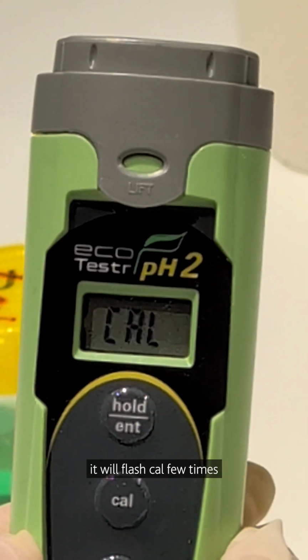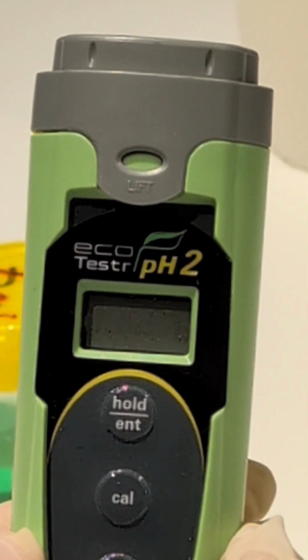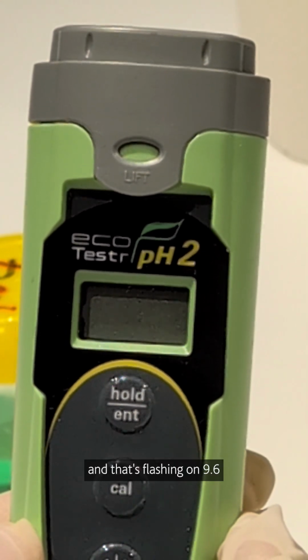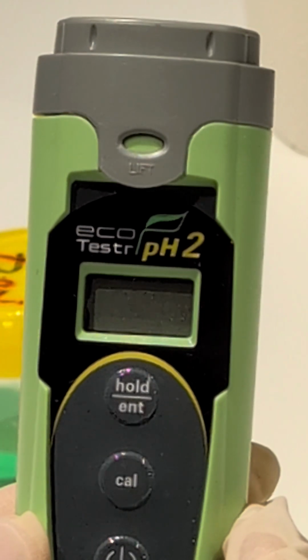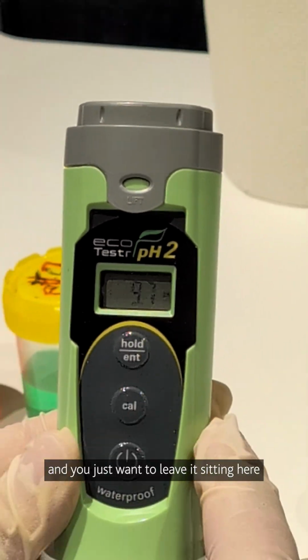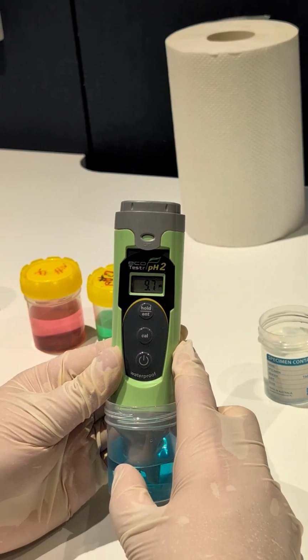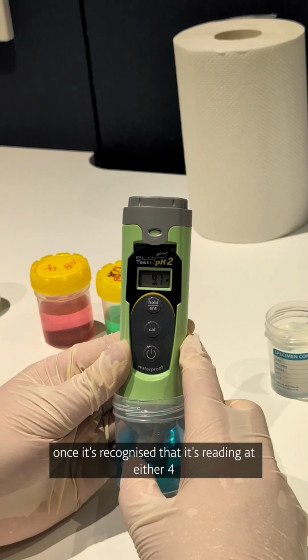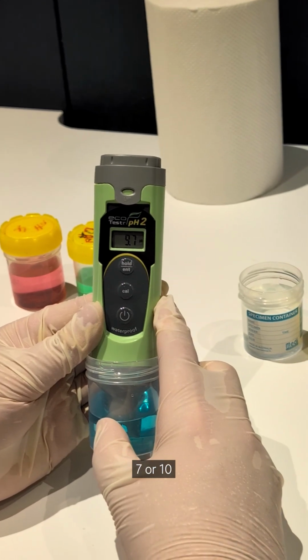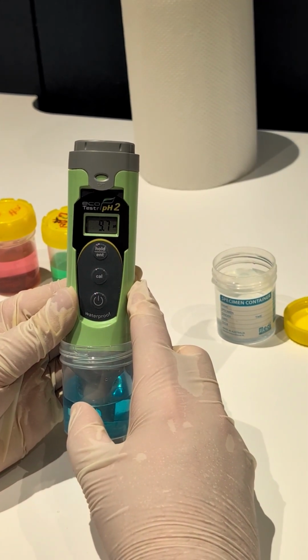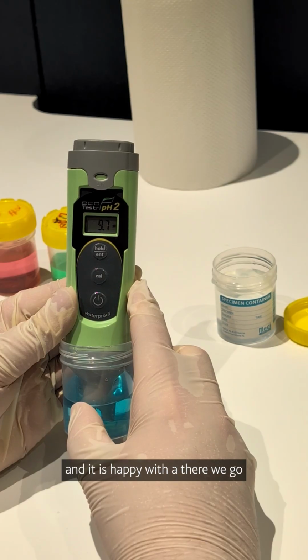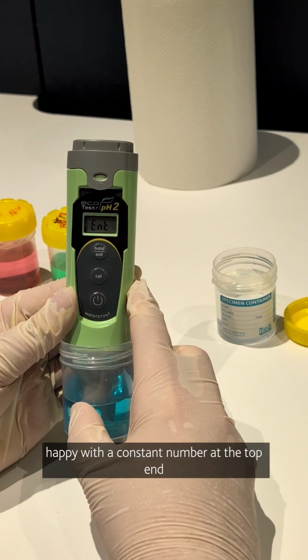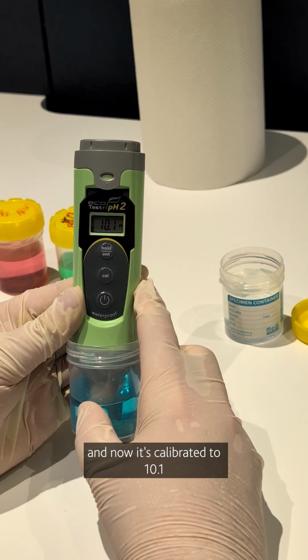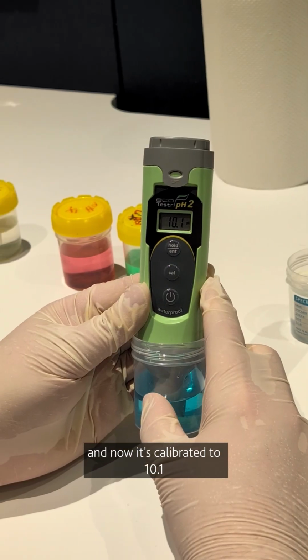It will flash cal a few times. And now it's flashing on 9.6. And you just want to leave it sitting here in the solution. Once it's recognized that it's reading at either 4, 7, or 10, and it is happy, with a constant number at the top end, it's now calibrated to 10.1.